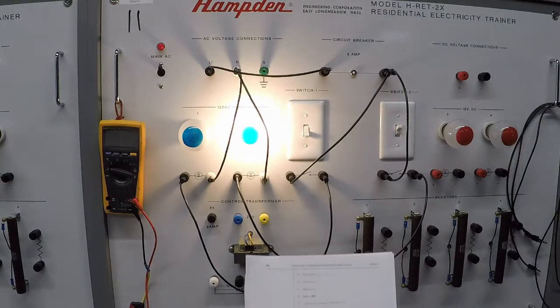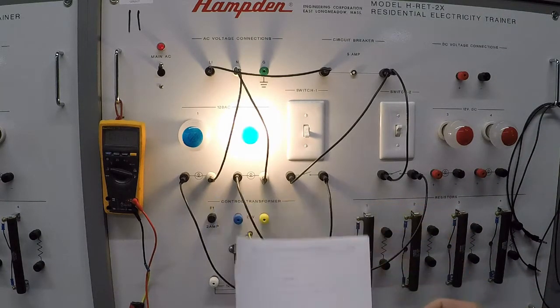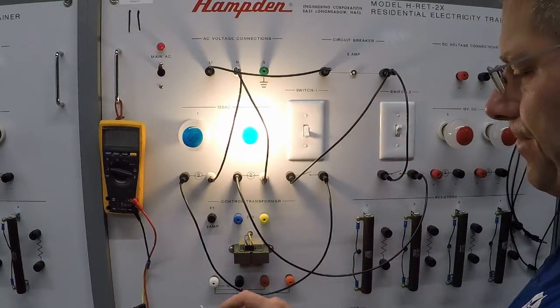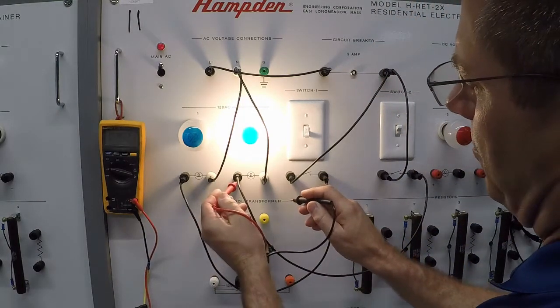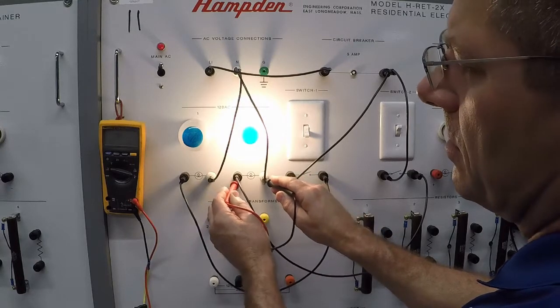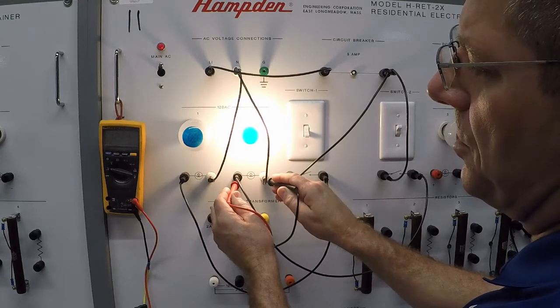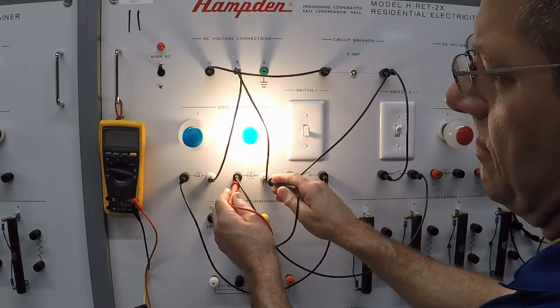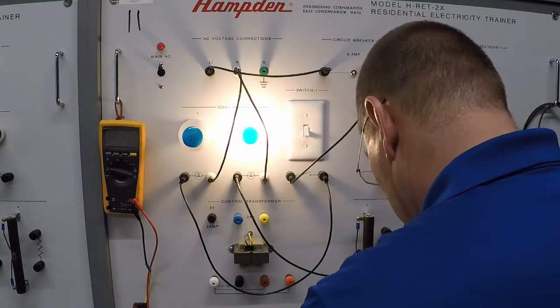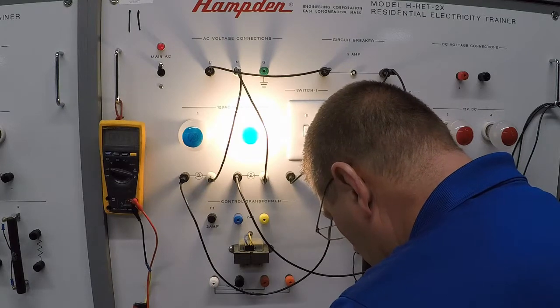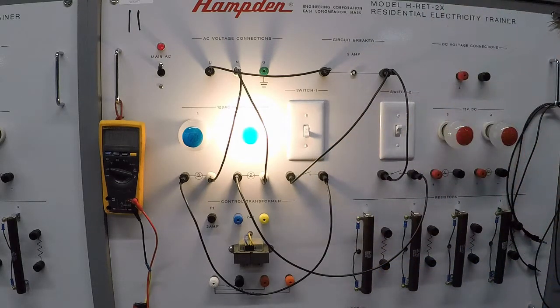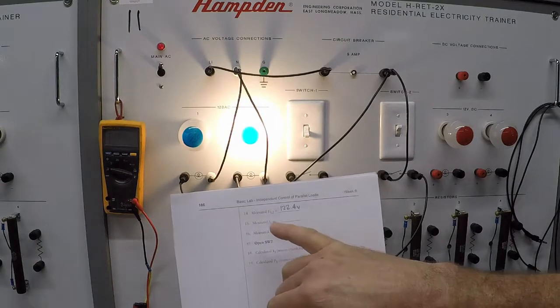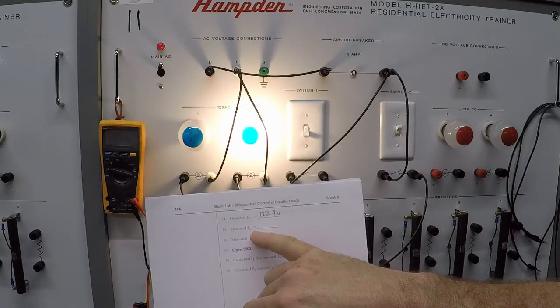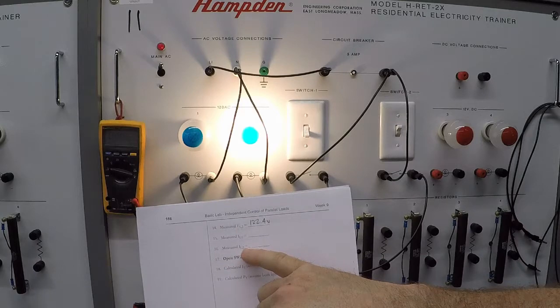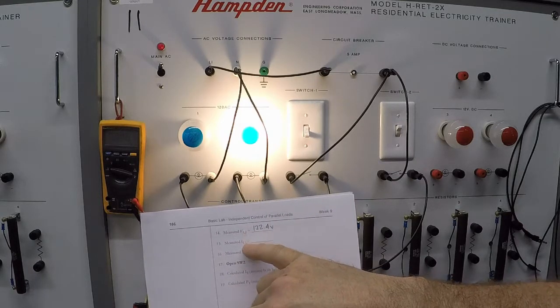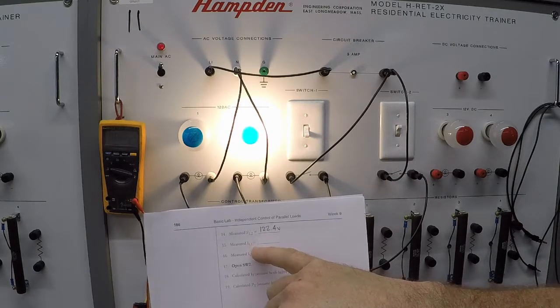Step 14 is measuring the voltage at EL2. Place the probes parallel to the load. We have 122.4 volts measured. We'll record that. In step 15, we're measuring IL1 and IL2.